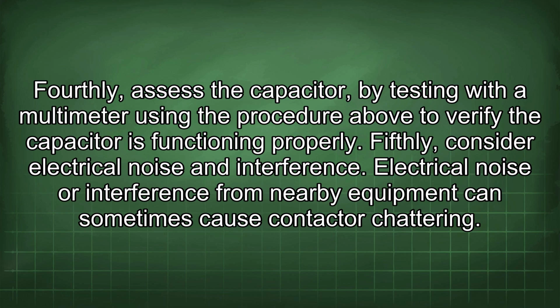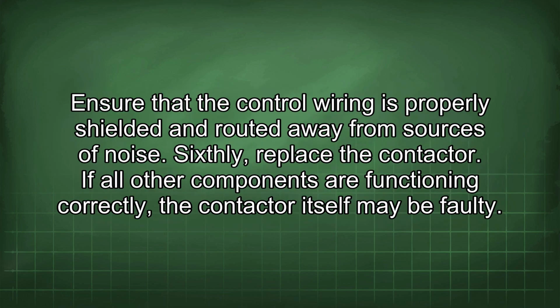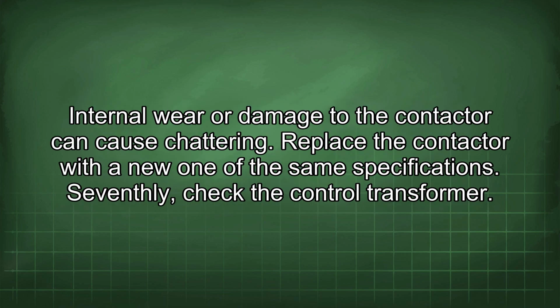Fifthly, consider electrical noise and interference. Electrical noise or interference from nearby equipment can sometimes cause contactor chattering. Ensure that the control wiring is properly shielded and routed away from sources of noise. Sixthly, replace the contactor. If all other components are functioning correctly, the contactor itself may be faulty. Internal wear or damage to the contactor can cause chattering. Replace the contactor with a new one of the same specifications.